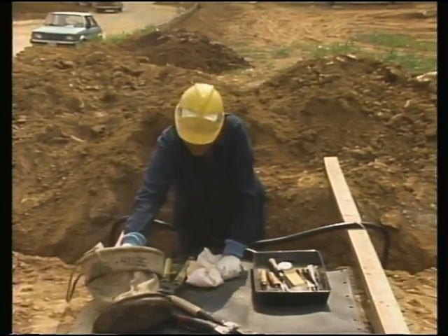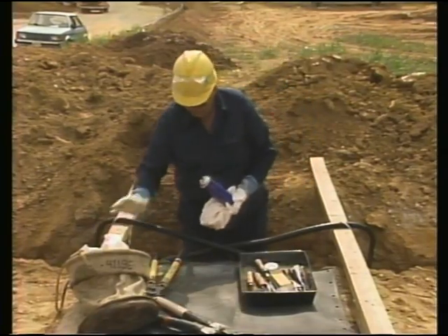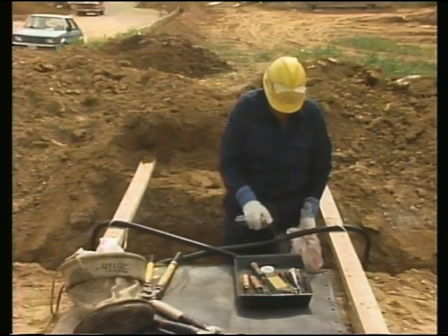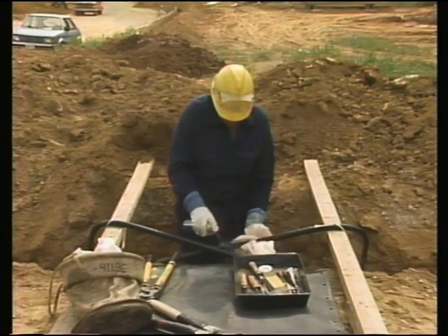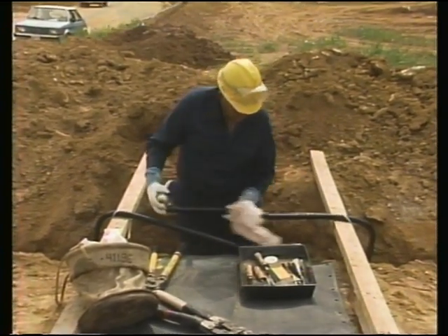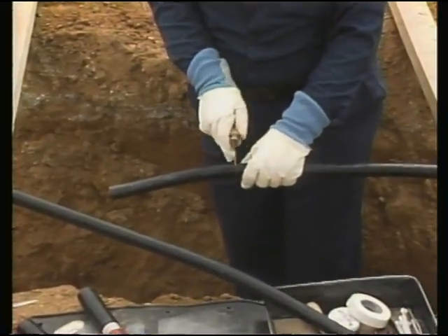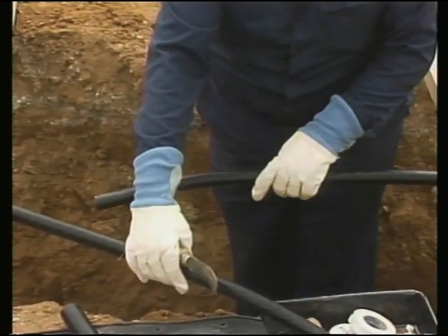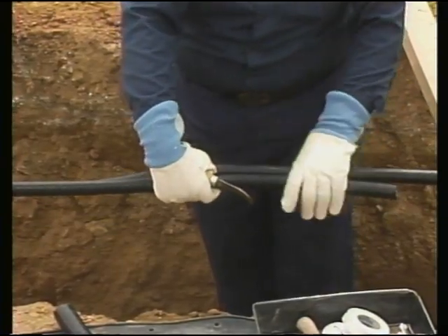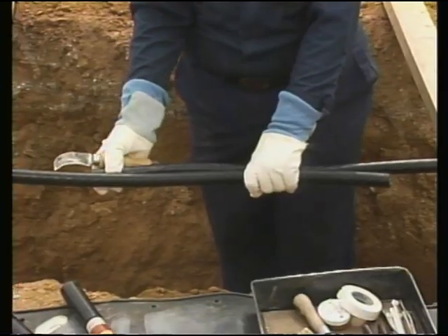And remember, the steps we're seeing here can only be used for this splice. Before cutting the cables, the workman cleans the cable jackets at the splicing area. This is to remove contaminants such as dirt and wax. The cables are overlapped and marked at the center line of the splice on each cable. The overlapping is done to make sure there is enough of the concentric wire to splice later.